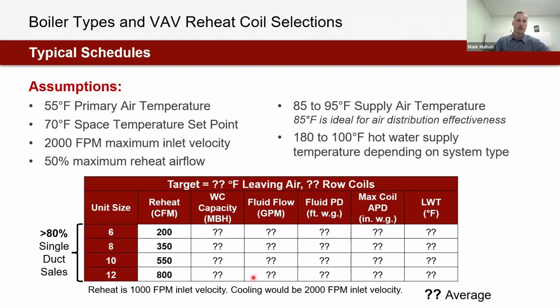And when we look at reheat, it is limited by ASHRAE 90.1 to be 50% of our design day cooling supply airflow rate. So generally speaking, we are going to see reheat being 50% of those values. That's what we see in this column I'm highlighting right here. So this is 1,000 feet per minute of inlet velocity, and that's going to be consistent throughout the presentation. A few other things we'll note. I'm assuming a 55-degree supply saturated air temperature from the air handler. I'm assuming that we're targeting somewhere in an 85 to 95-degree supply air temperature for heating. ASHRAE would indicate 85 degrees is ideal so that we can avoid stratification within the space, which would impact our air distribution effectiveness and the volume of ventilation air we need. And then I'll call out on every table: what is our hot water supply temperature? What is our leaving air temperature? What is the target here?